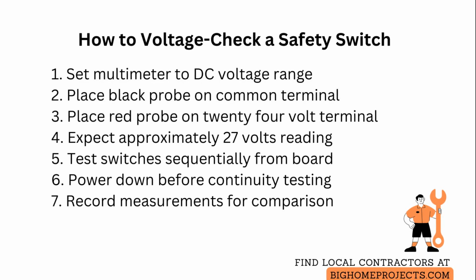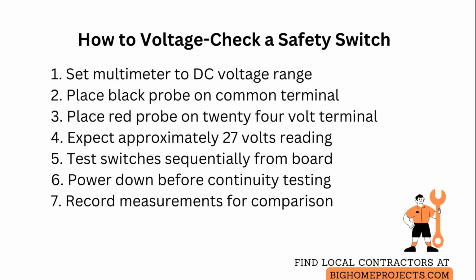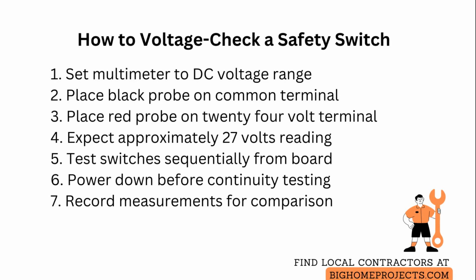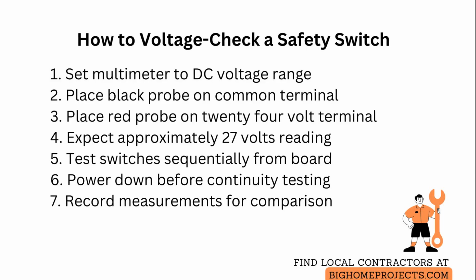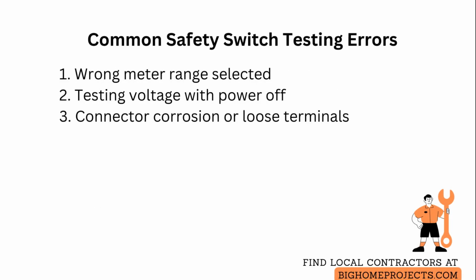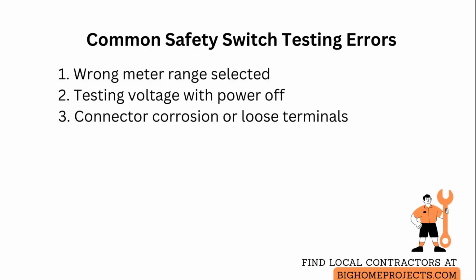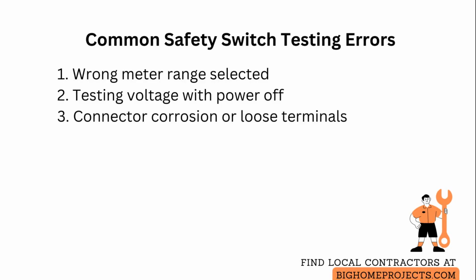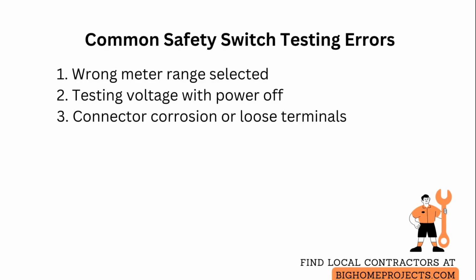Keep probe contact steady. Avoid touching metal parts with your fingers. And record each measurement so you can compare readings and identify intermittent faults. Common mistakes include measuring with the meter in the wrong range, which can give misleading or no readings. Correct this by selecting a voltage range that covers at least 30 volts direct current.